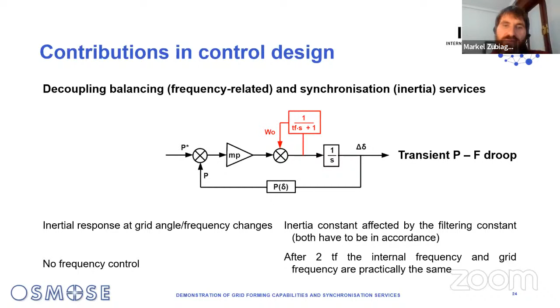Regarding the last control improvement, we worked on coupling the energy-intensive and power-intensive services. To do so, a microgrid was created on the DC side. Inside the converter, as Carmen pointed out, we have three DC-DC converters, and these three DC-DC converters regulate the bus voltage together. By control settings, we can make some of them — especially the ones related to the ultracapacitor energy storage devices — have really fast response to any change in the DC bus voltage.